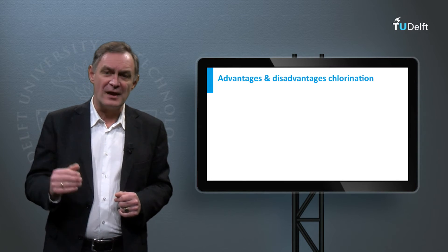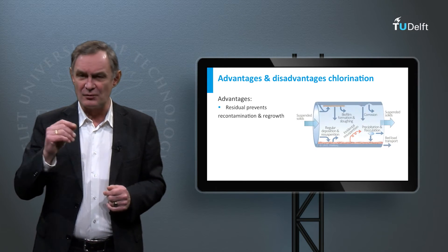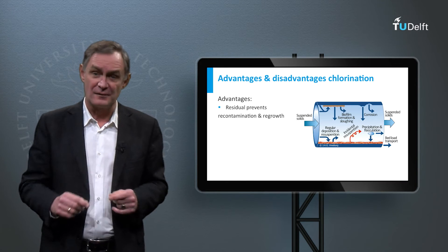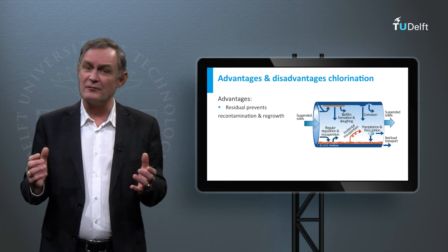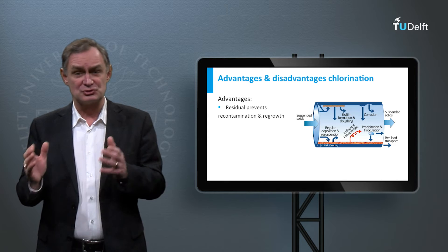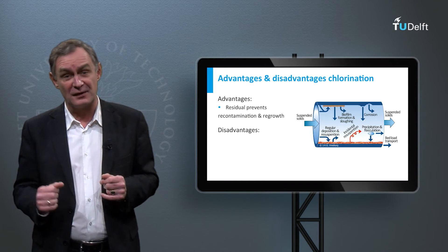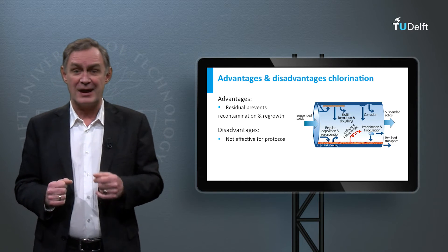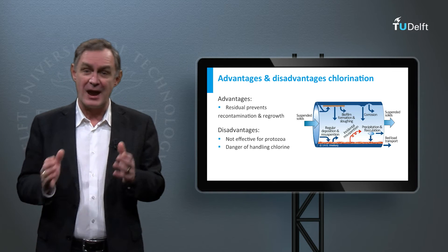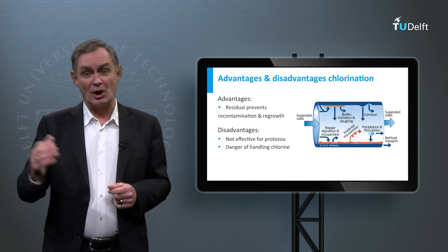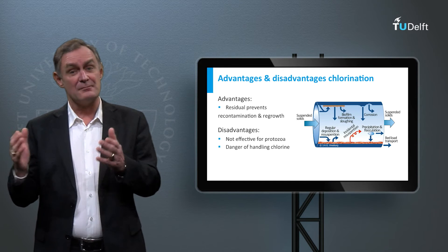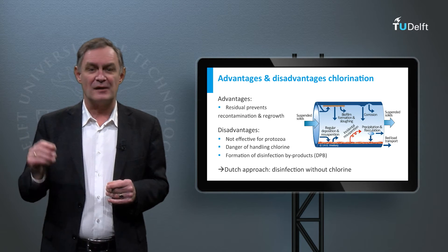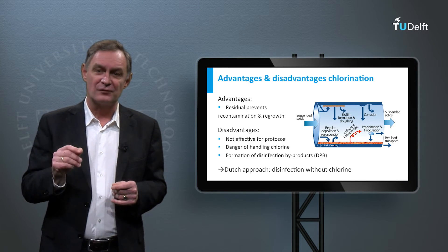The main advantage of chlorine is that it provides a residual and can thus be used as transport chlorination to prevent regrowth in the distribution system. However, the use of chlorine has also some downsides. It is, for example, less effective for protozoa. In addition, since it is a strong oxidant and extremely corrosive, special storage and handling measures should be taken. The other disadvantage is the formation of disinfection by-products. Therefore, chlorination is no longer applied in water treatment in the Netherlands.